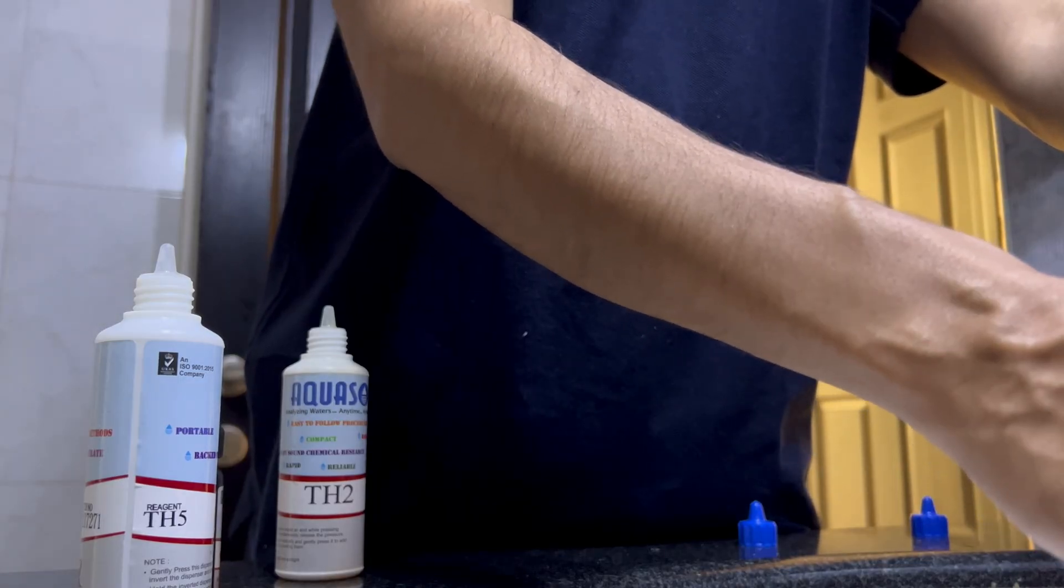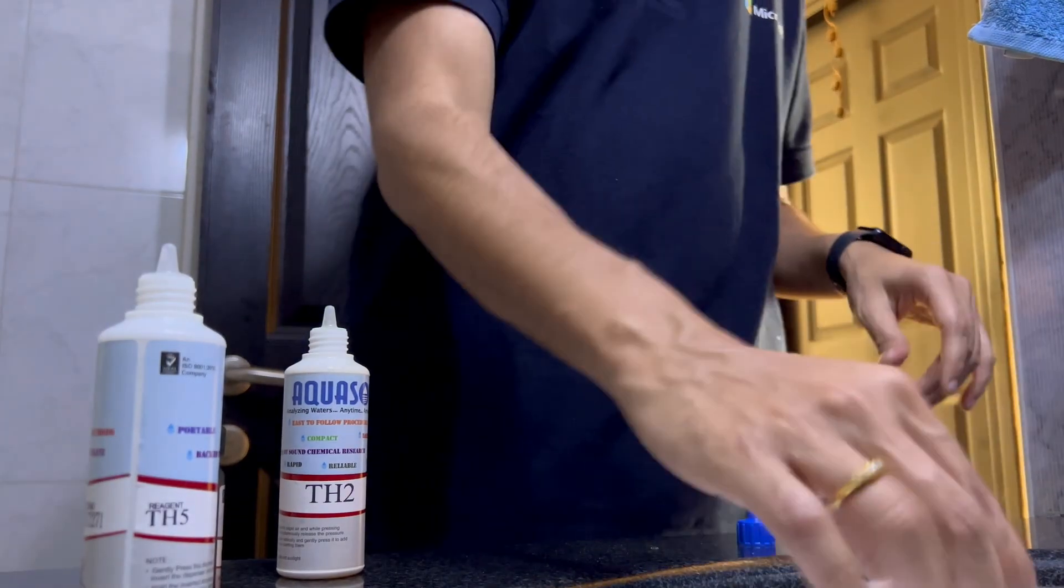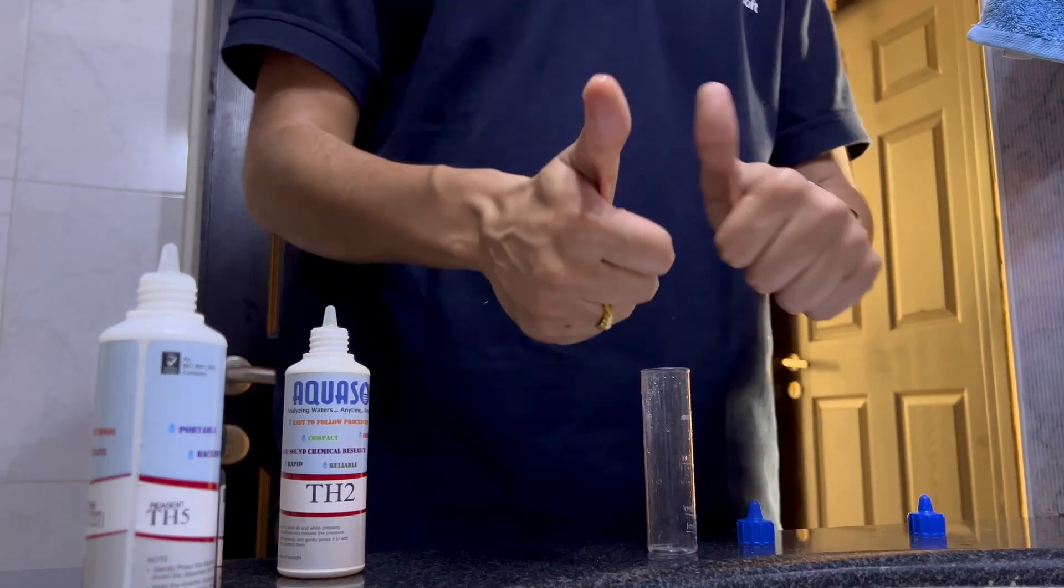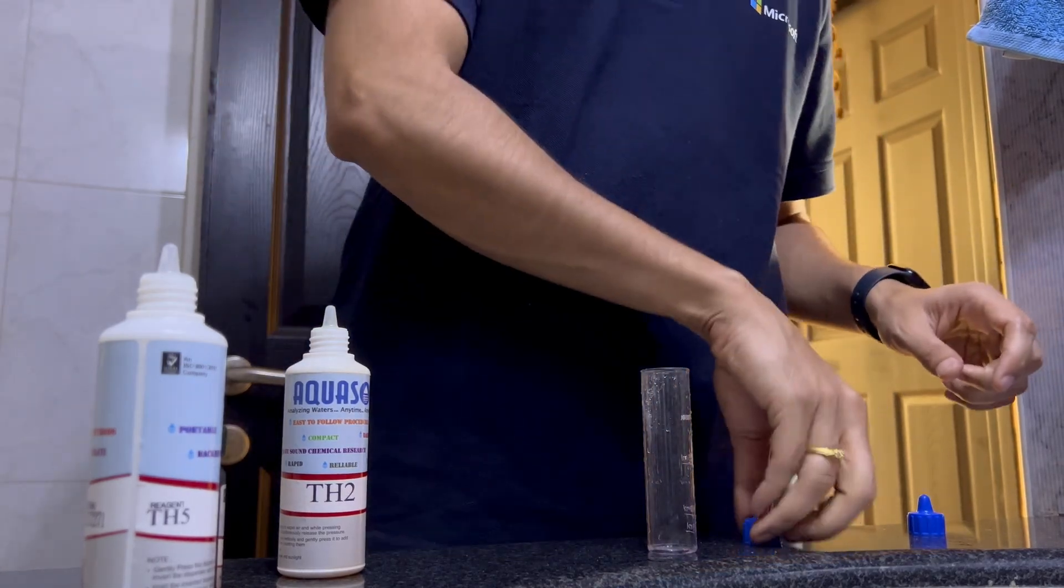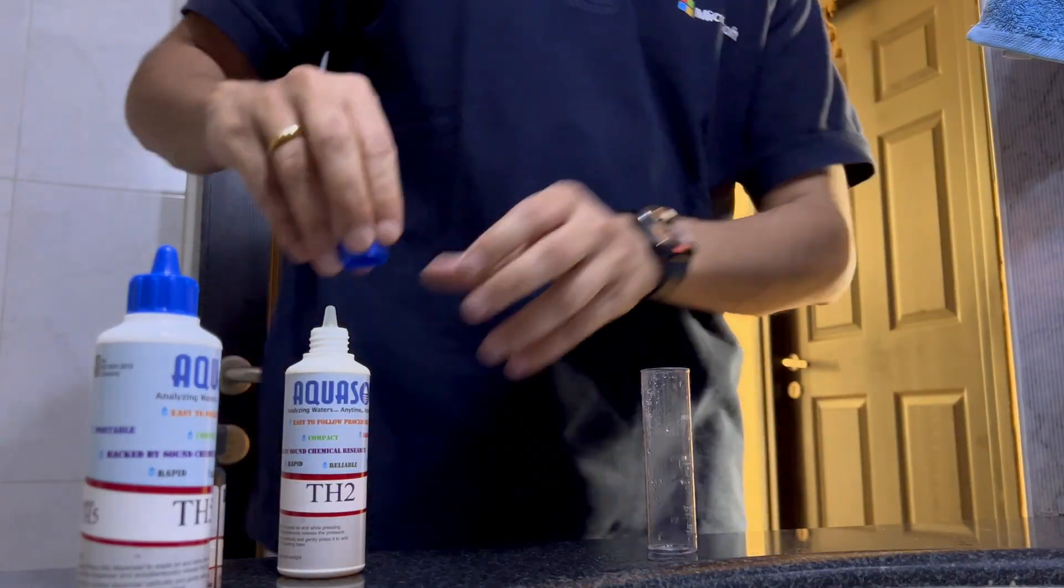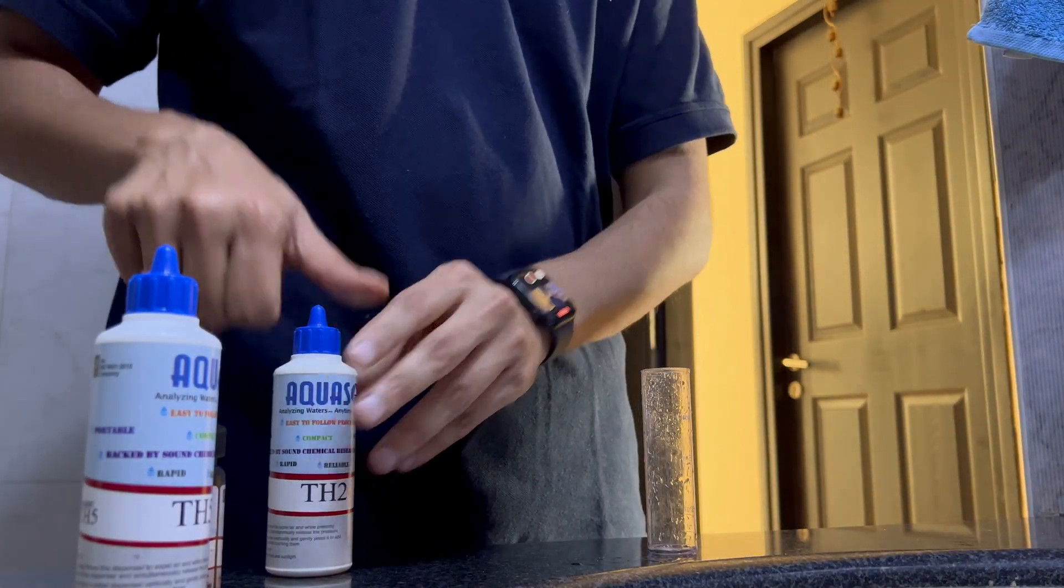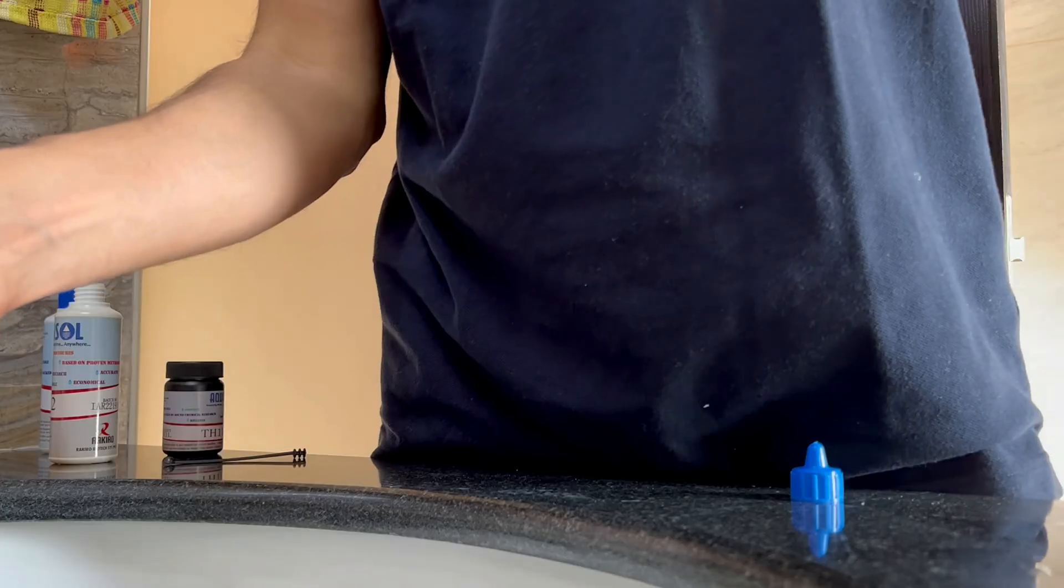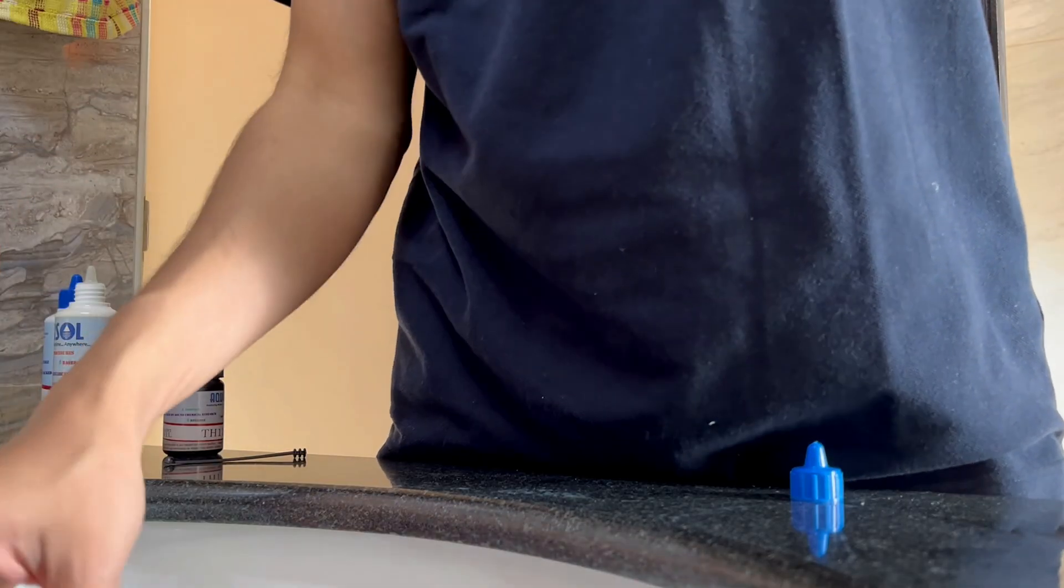It has changed to blue so it took more than 30 drops. I'm sure I've got a couple of drops more while I was inserting the drop so let me take the bare minimum 30 as the number. 30 multiplied by 25 is 750 so that's the current hardness of the water. Let's go back to the other bathroom and test the softened water from the softener and see the results.